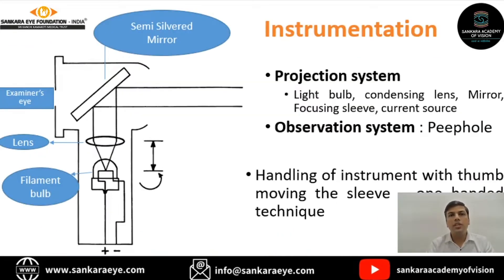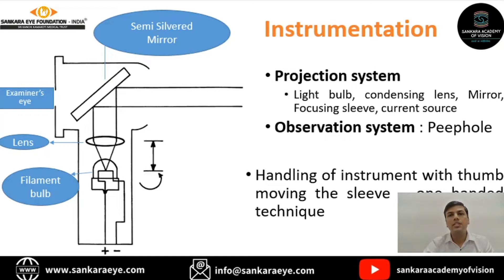Coming to the parts of the retinoscope: the instrument is attached to a battery, which can be rechargeable or disposable. This connects to a filament bulb as the light source, followed by a condensing lens that focuses the light rays. There is a peep hole where the examiner observes, and the light from the condensing lens is focused on a semi-silvered mirror, allowing the reflected light to be seen through it.